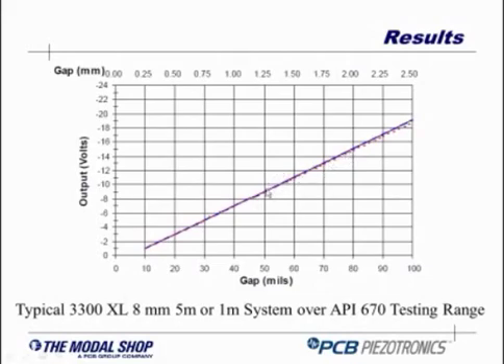So if you're about 50 mils, or halfway through the linear range of the prox probe, 1.25 millimeters, you expect to see about minus 10 volts DC coming out of the prox probe. You can do that test with the shaker turned off - it's just a static test. You just move the prox probe away from the target, and that's what most people do out there.